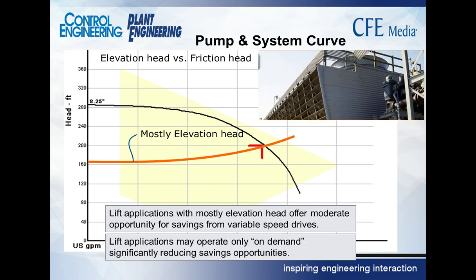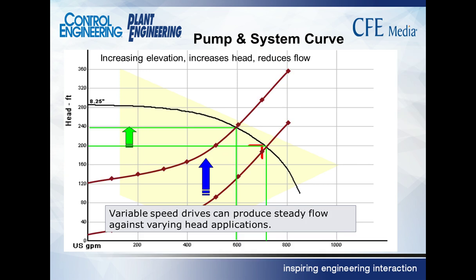An elevation system, on the other hand, does not have as much opportunity for savings because the head is not changed as much. Also, on many of the systems that are high lift, high elevation applications, you have the opportunity to turn the pump on and off rather than control its speed. That also limits the amount of savings that you could get from a variable speed drive.